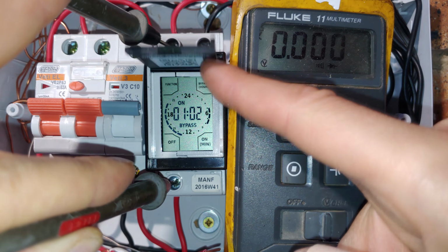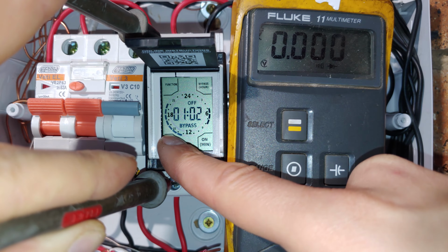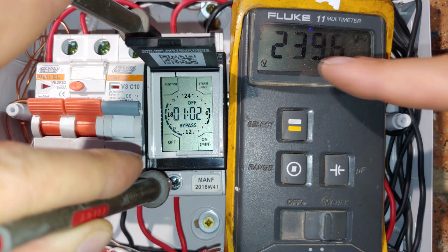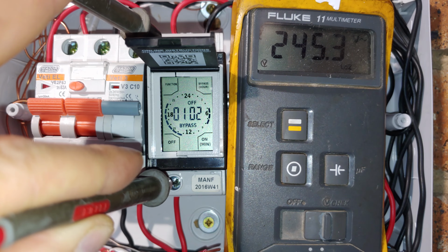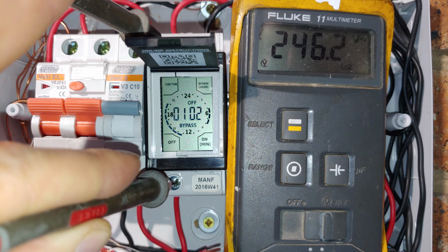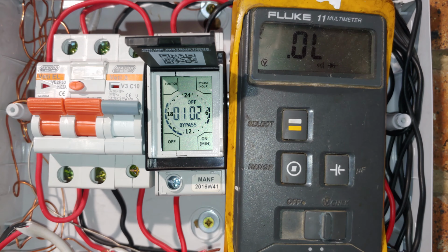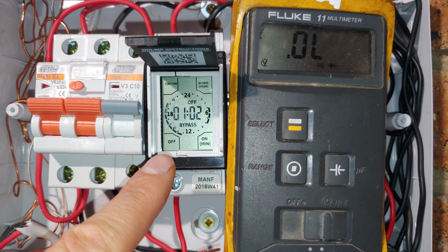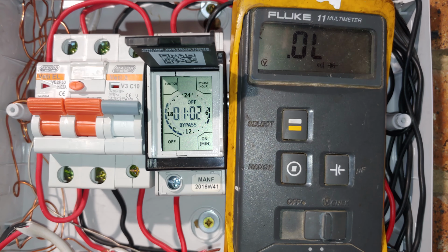If I switch the timer off, you can see that now I'm seeing 240 odd volts there, showing me that the timer is in an open circuit condition. Even though the circuit breaker is still in the on position, the timer has blocked the current flow, meaning that the timer is now controlling when the pool pump will go on and off.